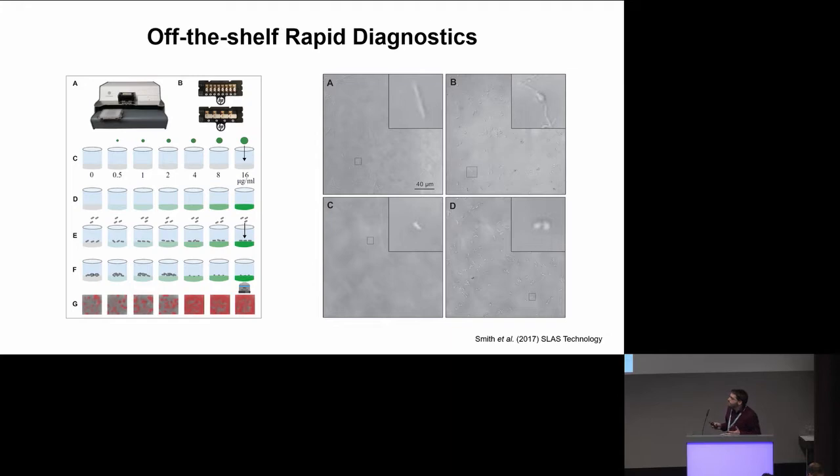So in our case, we load these little cartridges with antimicrobials and prepare dilution series, just like a standard broth microdilution panel, within the wells of a 384 well plate that are actually coated by a microscopically compatible solid surface so that the cells are sitting in a nice layer that we can focus on. After we dispense these droplets of antimicrobials, we develop the concentration gradient, which is then overlaid by bacteria, which are also dispensed using the inkjet technology here.